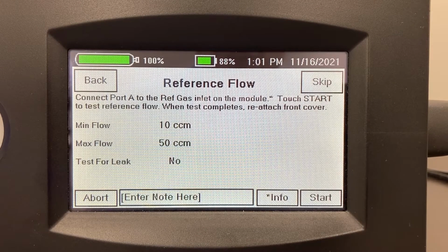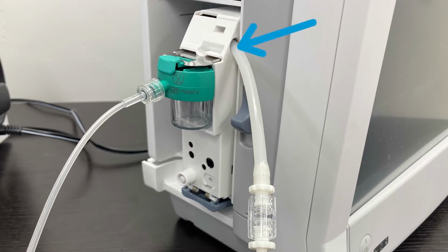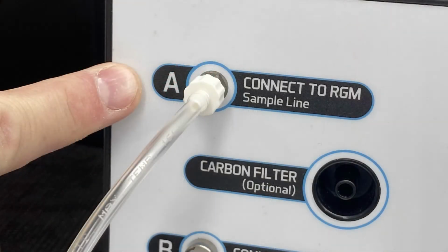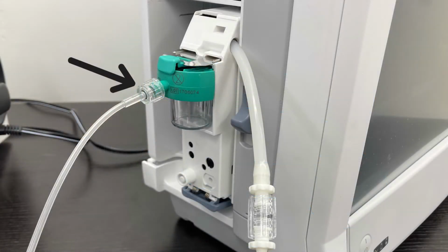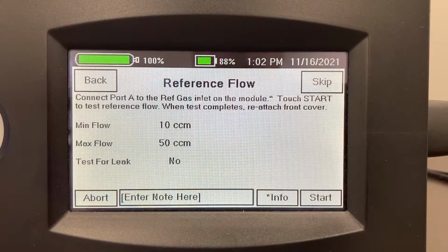Next, we're going to measure the reference flow rate. We've got to connect a line between the reference port, that's the reference gas port that's on the side of the module. You can only see this reference port with the front cover off of the module. And then we'll connect the other end of that to port A on the SmartTank. Remember to leave the regular sample line that's connected to the water trap, leave that connected to the module. Once it's connected, press start.